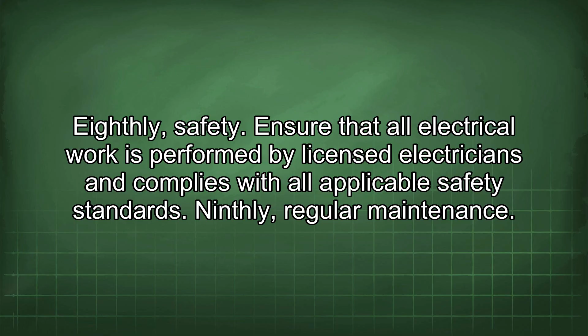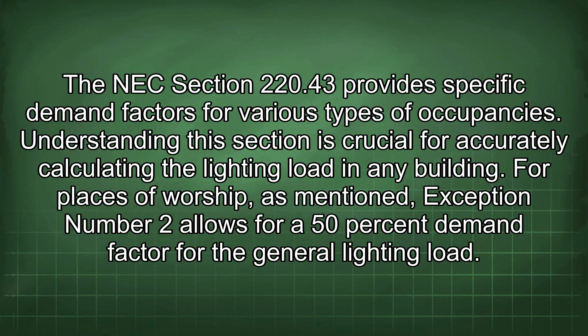The NEC Section 220.43 provides specific demand factors for various types of occupancies. Understanding this section is crucial for accurately calculating the lighting load in any building. For places of worship, as mentioned, exception number 2 allows for a 50% demand factor for the general lighting load. This exception recognizes the intermittent use of lighting in these facilities.